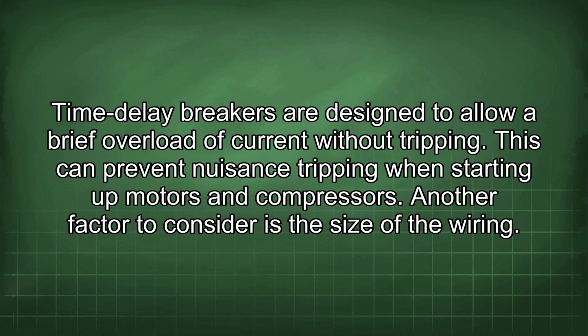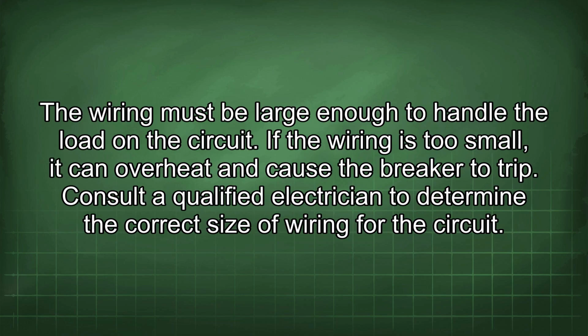Another factor to consider is the size of the wiring. The wiring must be large enough to handle the load on the circuit. If the wiring is too small, it can overheat and cause the breaker to trip. Consult a qualified electrician to determine the correct size of wiring for the circuit.